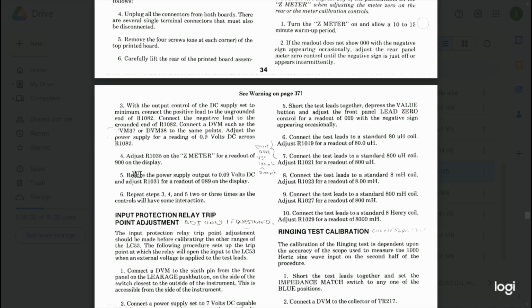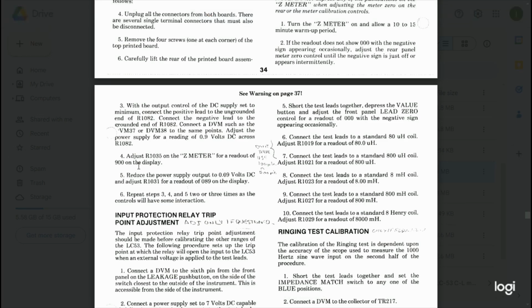And it says reduce the power supply output to 0.09 volts DC as measured on the DVM, and adjust R1031, which is our culprit, for a readout of 0.89 on the display. I was having difficulty doing that, and apparently if you don't have the capability of making this adjustment, it's going to cause problems with a lot of other readouts on the meter.